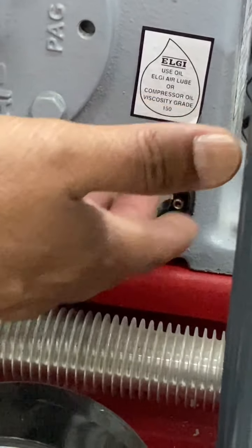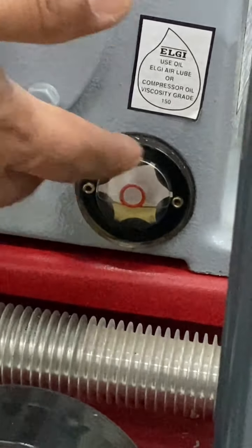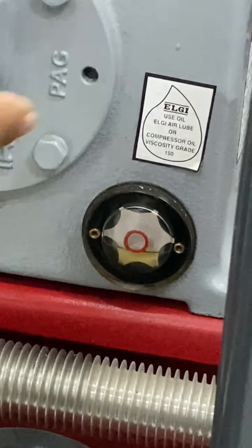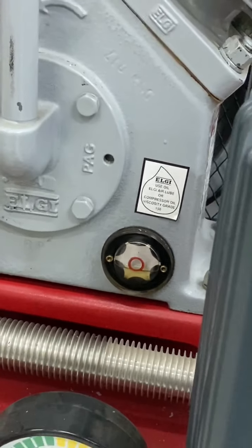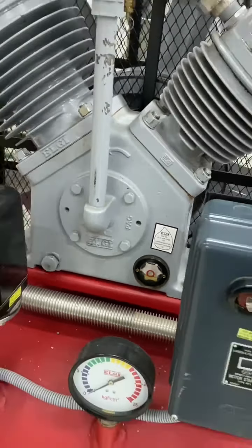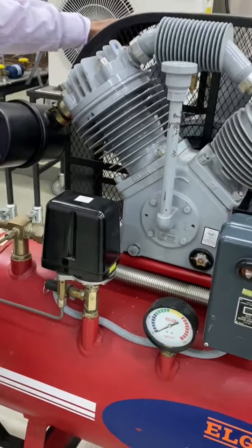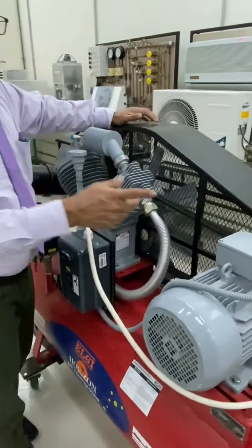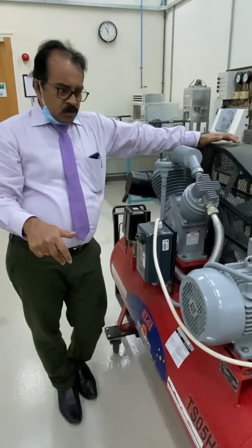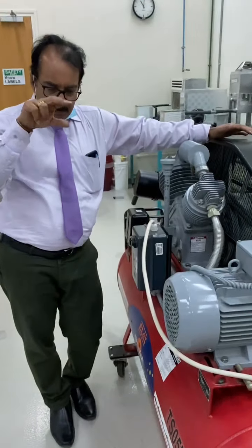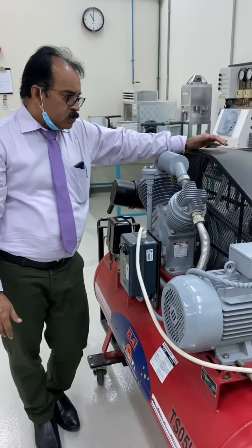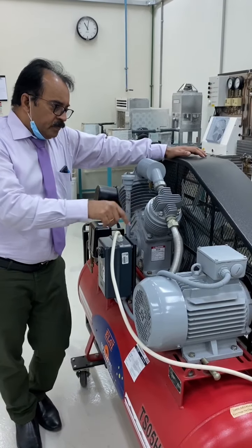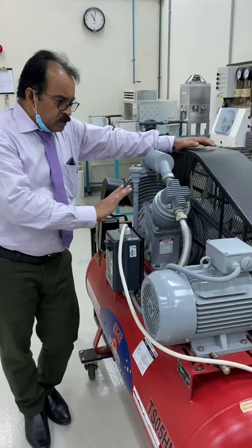That is very important. If it is more than 50%, that means the crankcase has enough oil to run the machine. And also check the belt. You must remove the machine guard, take it out and check the pulley, and also check the belt for any crack, or whether the belt is loose, like we did last lab. We check the deflection of the belt, and also the glue of the belt, and those things we should check.